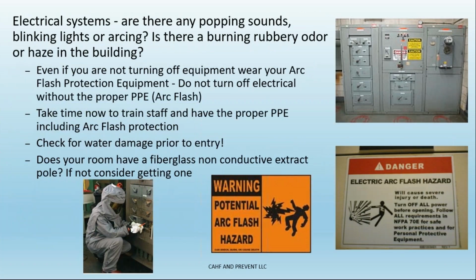After the earthquake occurs and you're going through the RACE process, you have to pay attention to the lighting and the electrical systems. If you smell burning or hear popping or sputtering sounds, that may be an indication of an electrical component that is compromised. Your staff should have arc flash protection and be trained on how to don the equipment. Prior to entering an electrical room, check for indications of water presence.